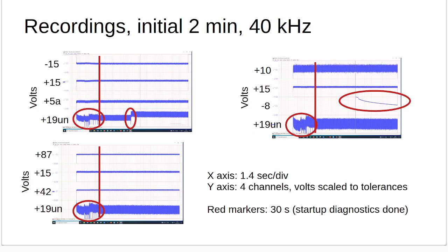Now, these are 3 separate screenshots, and in each screenshot you can see 4 channels being recorded. These are in this case all analog channels. If we take the upper left image here, you see the 4 channels that have been recorded, and you can see first of all the plus 19 volt unregulated, that's the one that goes to the fan, unregulated. These little spikes that go down, I think this is relay switching or something like that. I can actually hear these relays switching on and off, and you'll notice that those spikes are not seen on any of the regulated voltages.